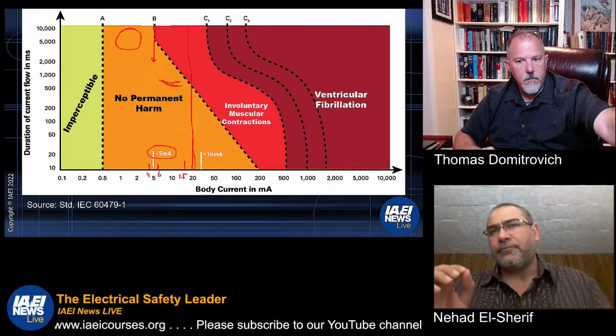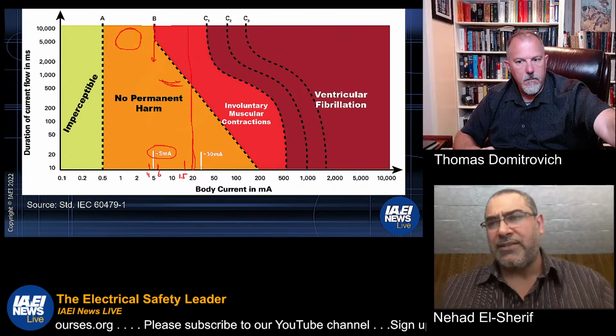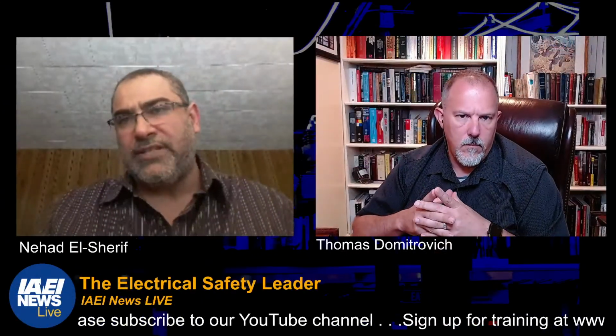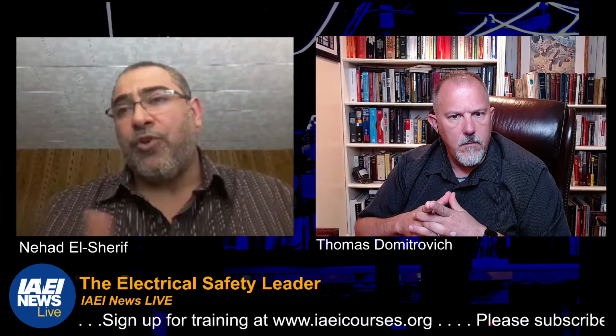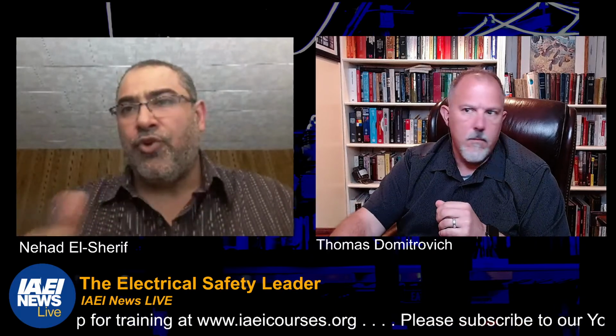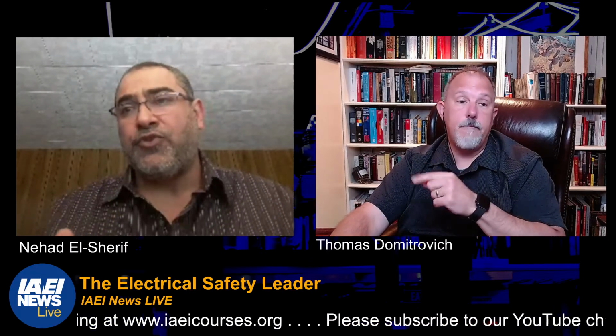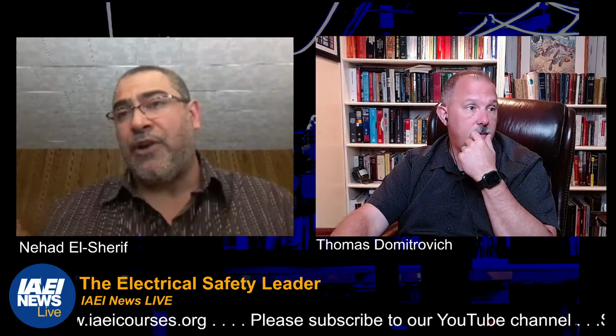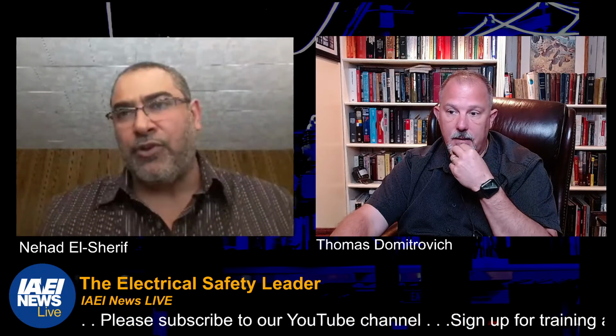The UL, which is something I don't think we're covering here on the slides, I'll just talk about it quickly. The idea of UL to increase the trip level from 6 milliamp, 5 plus or minus 1, to 20 is under the assumption that we have reliable grounding. So remember the equipment grounding conductor, you only do this when you have what you refer to as reliable grounding, which means you have an equipment grounding conductor. We don't have this for Class A. Class A, you're not required to have an equipment grounding conductor connected to the piece of equipment you're protecting.